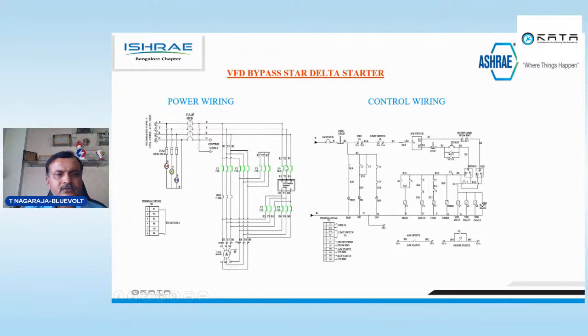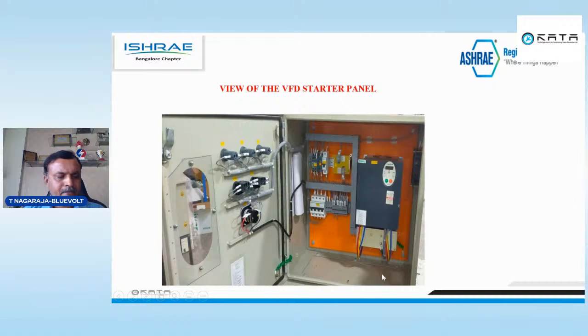There is not much difference from the direct-on-line starters. The control circuit will be the same as it is. This is only the VFD starter, so there is no bypass here. It is a VFD with one auxiliary contactor.